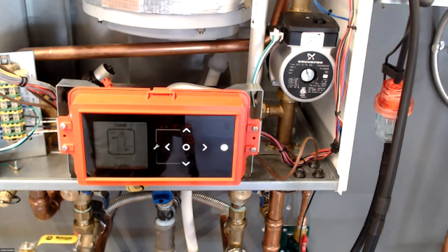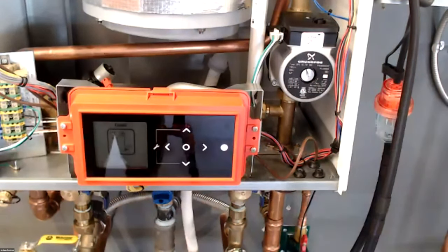So that's just one thing to note. Gotten that call a couple times. Hate to have you guys have to put one in and then cut it out. So on the combis, no check valves on the return lines. Keep that open. That way the system, when it's in domestic, has thermal expansion all the way through it. Okay.